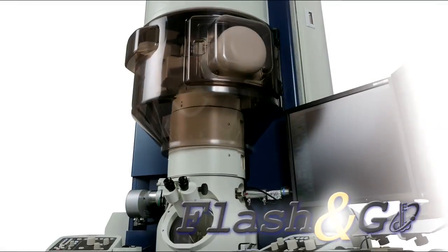With conventional cold FEG, emission stability degrades quickly due to residual gases in the area of the tip. The operator must then flash to clean off the tip after a few hours of use, then wait up to half an hour to resume imaging.